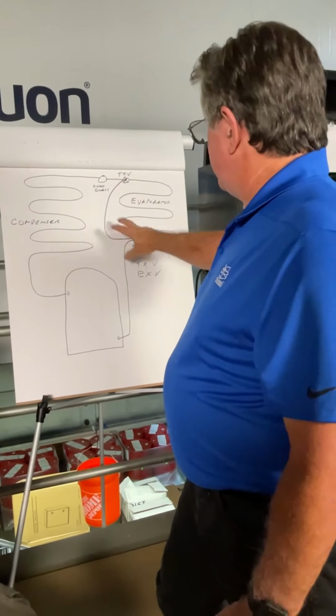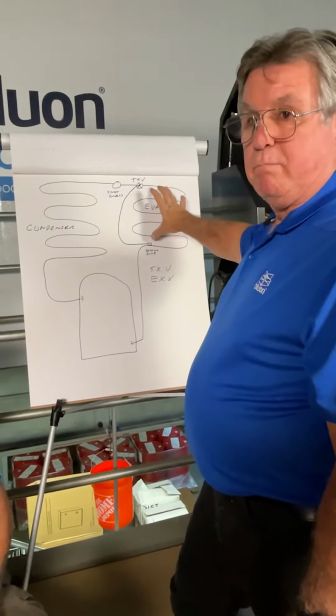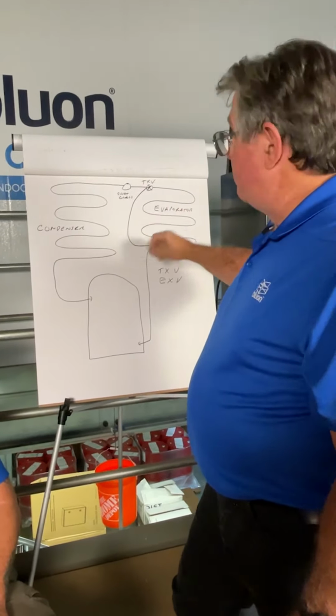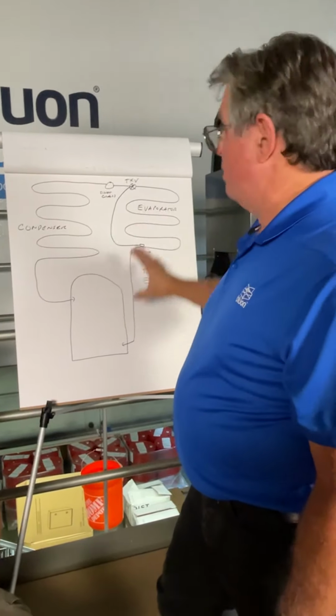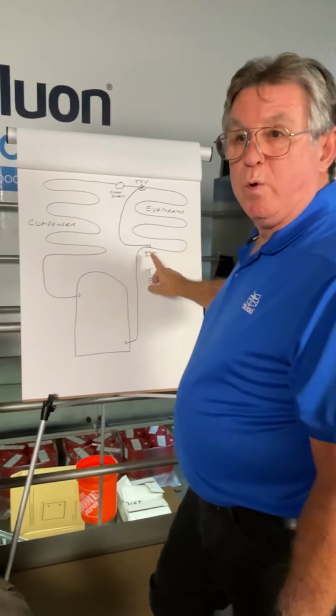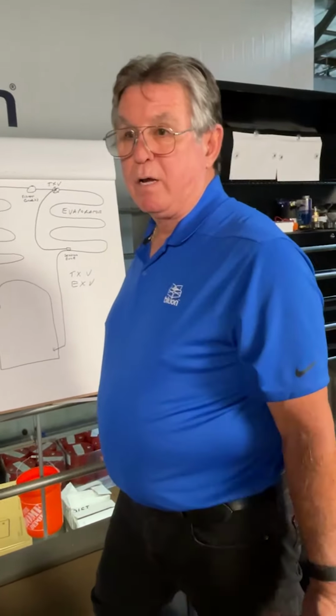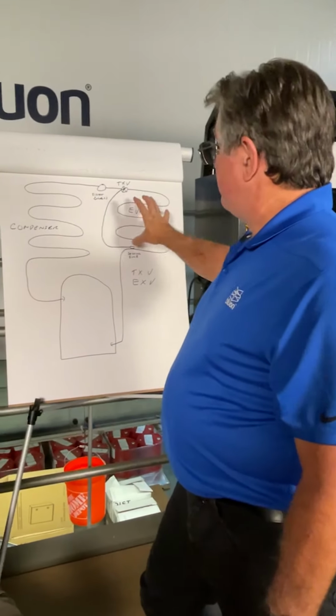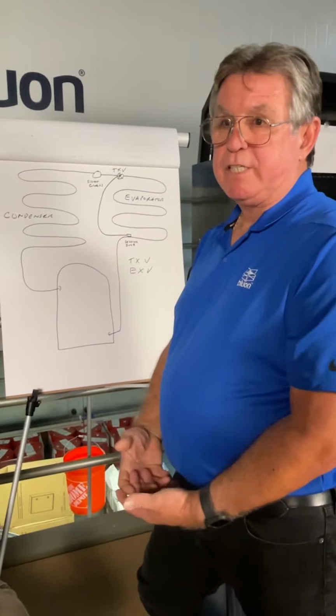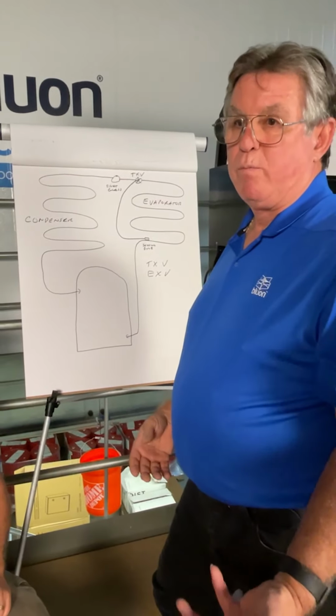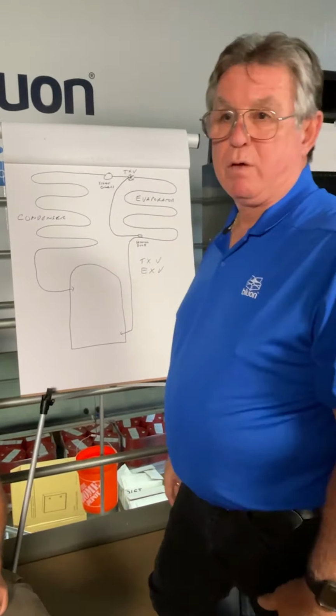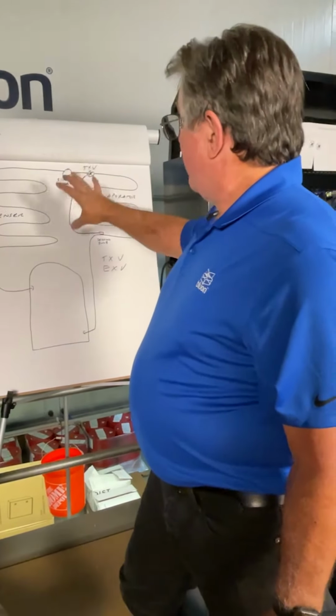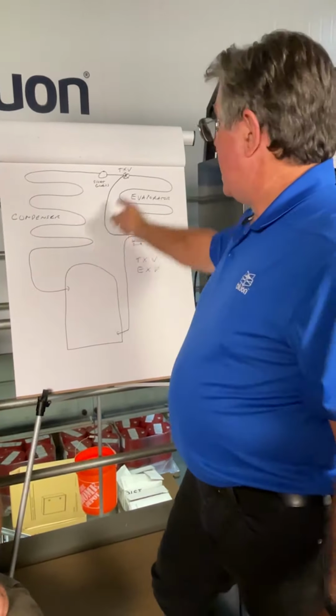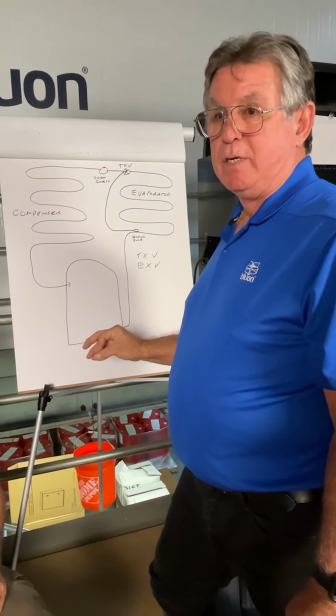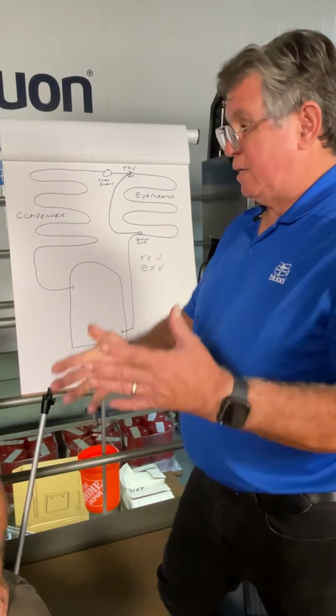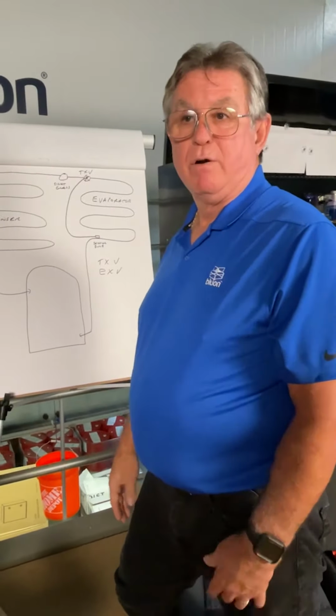So I think you can see here, if I'm controlling my refrigerant in this coil, I don't care what the outdoor temperatures are. I don't care about any of that other kind of stuff. This is simply looking at what's going on in the coil, and it's responding accordingly. So by using this, we're a lot more efficient, and so we're not running the system and only feeding part of the coil. So I think you can see why having an active device that's responding to the system is going to be more efficient than a cap tube or piston or things like that.